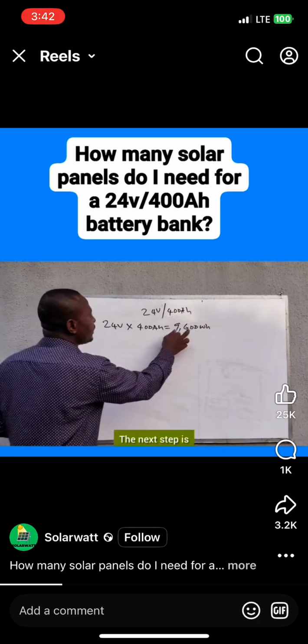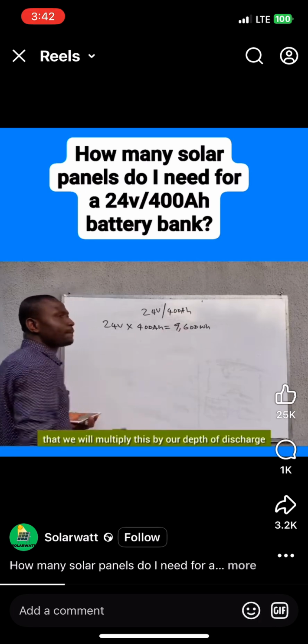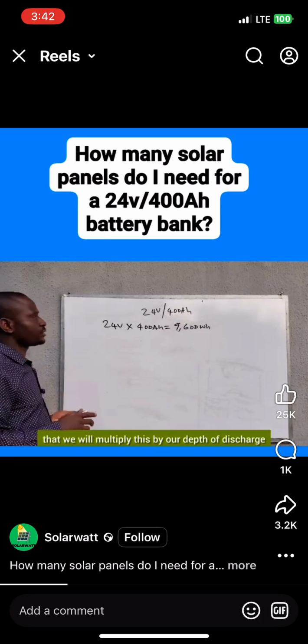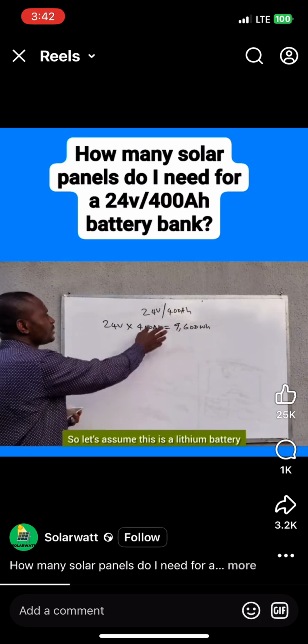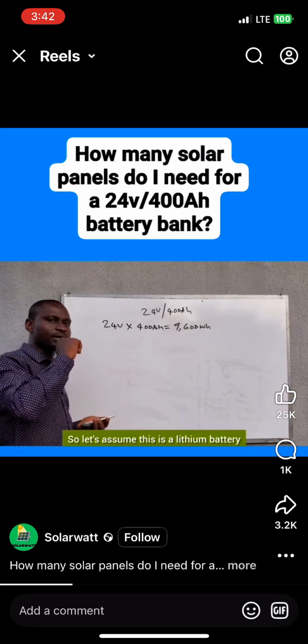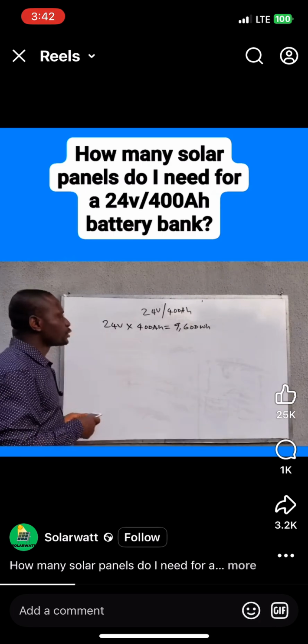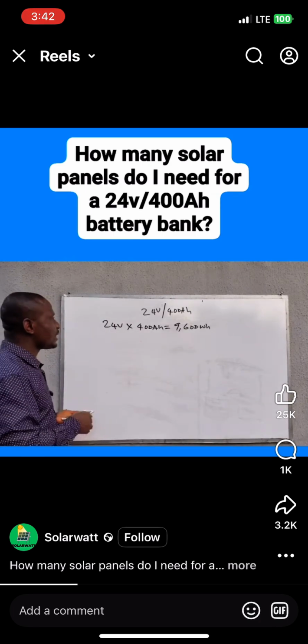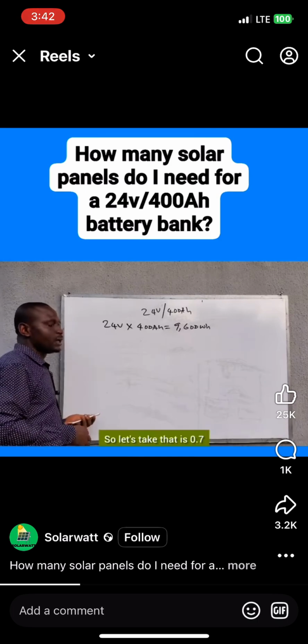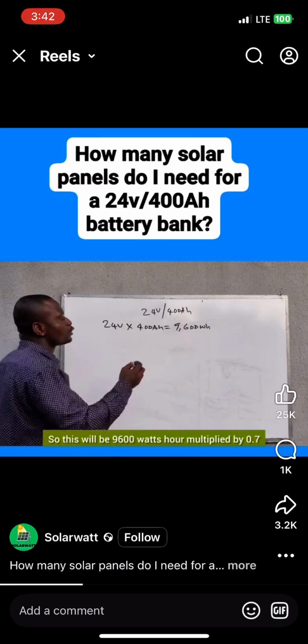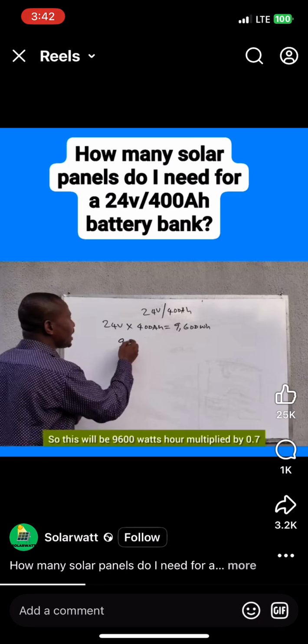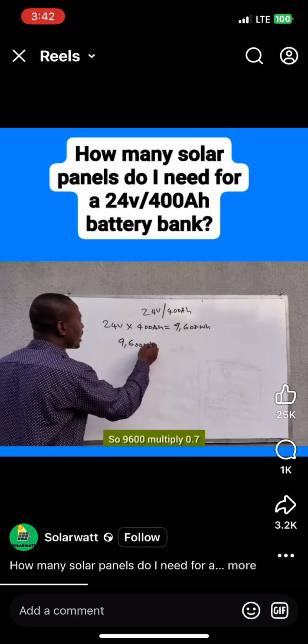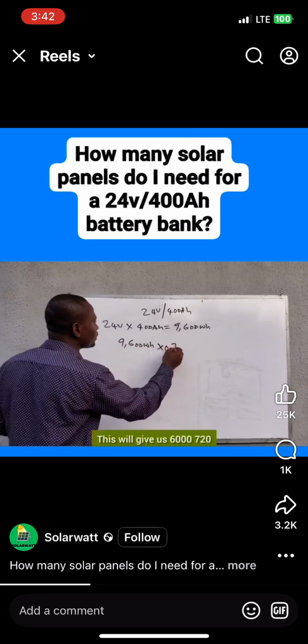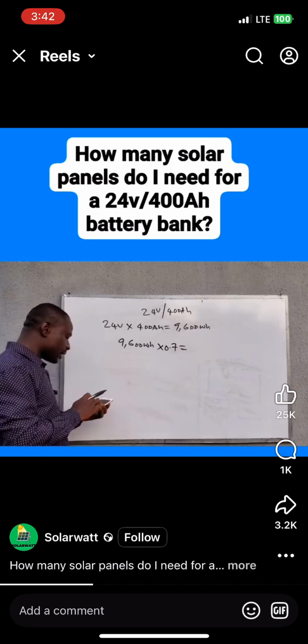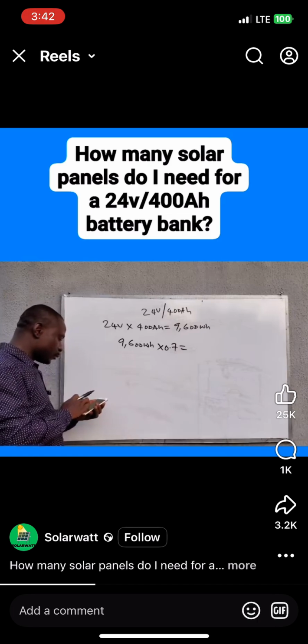So we want to know the number of solar panels. The next step is that we will multiply this by our depth of discharge. Let's assume this is a lithium battery or a flooded battery, so we are going to use 70% DOD, which is 0.7. So this will be 9,600 watt hours multiplied by 0.7.